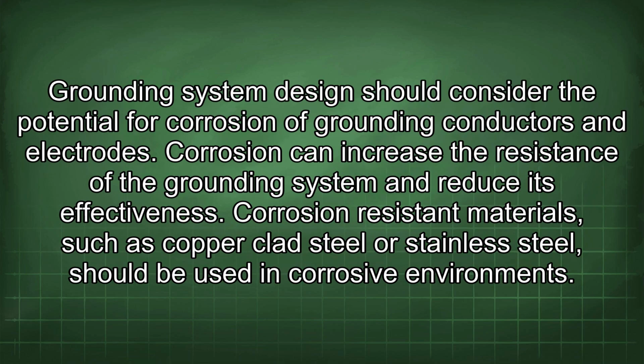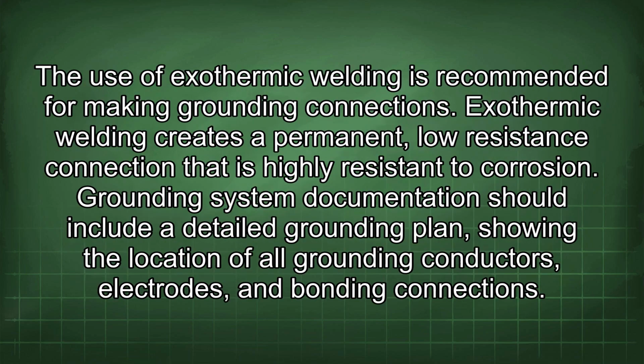Grounding system design should consider the potential for corrosion of grounding conductors and electrodes. Corrosion can increase the resistance of the grounding system and reduce its effectiveness. Corrosion-resistant materials, such as copper-clad steel or stainless steel, should be used in corrosive environments. The use of exothermic welding is recommended for making grounding connections. Exothermic welding creates a permanent, low-resistance connection that is highly resistant to corrosion.